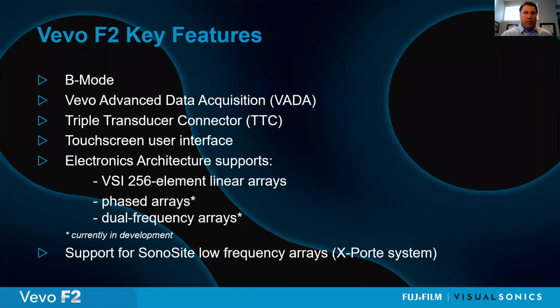The system does come equipped with standard B-mode imaging. I mentioned the Vevo Advanced Data Acquisition. New to our platforms is the addition of a triple transducer connector. This allows us to connect multiple transducers at the same time to the system. We have a touchscreen user interface, as mentioned. The electronics now support all of our standard 256 element linear arrays. We do support phased arrays and dual frequency arrays, some of which are currently in development, and I'll share a few examples of those with you shortly.